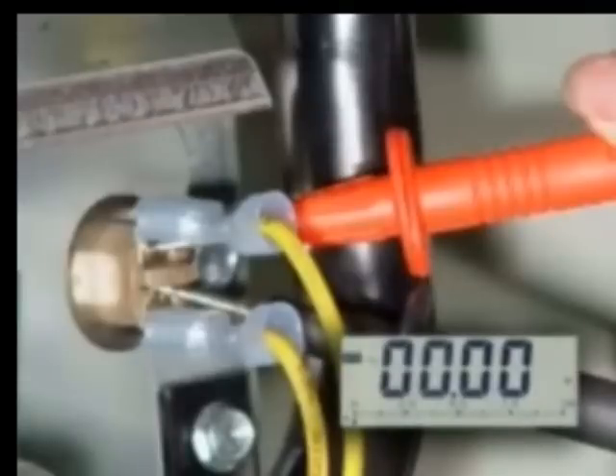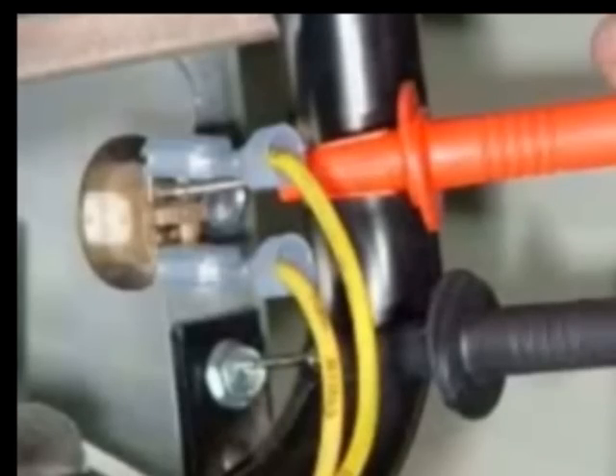If you measure zero volts across the high limit yet the furnace is indicating an open limit fault, check for 24 volts to ground at each side of the switch. If you do not measure voltage, another limit switch is open.